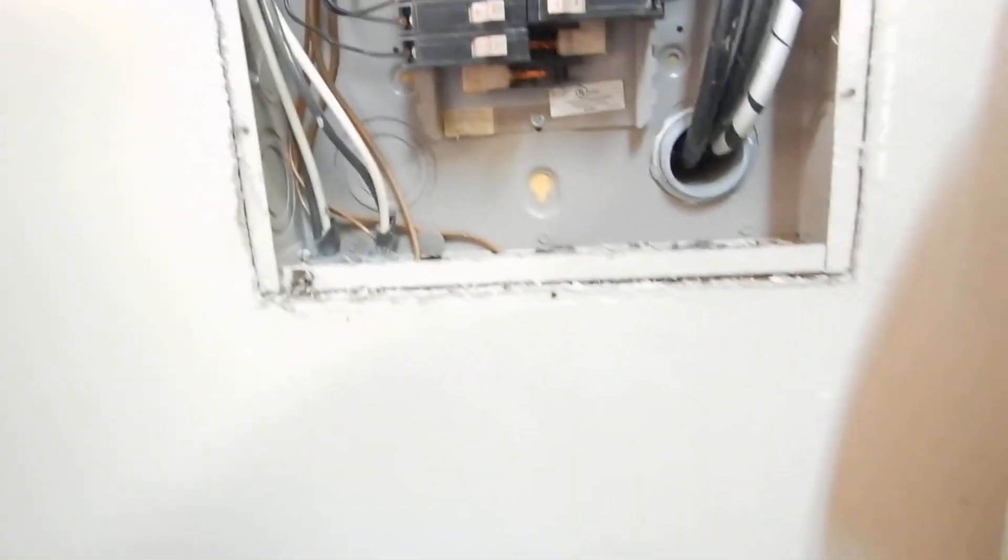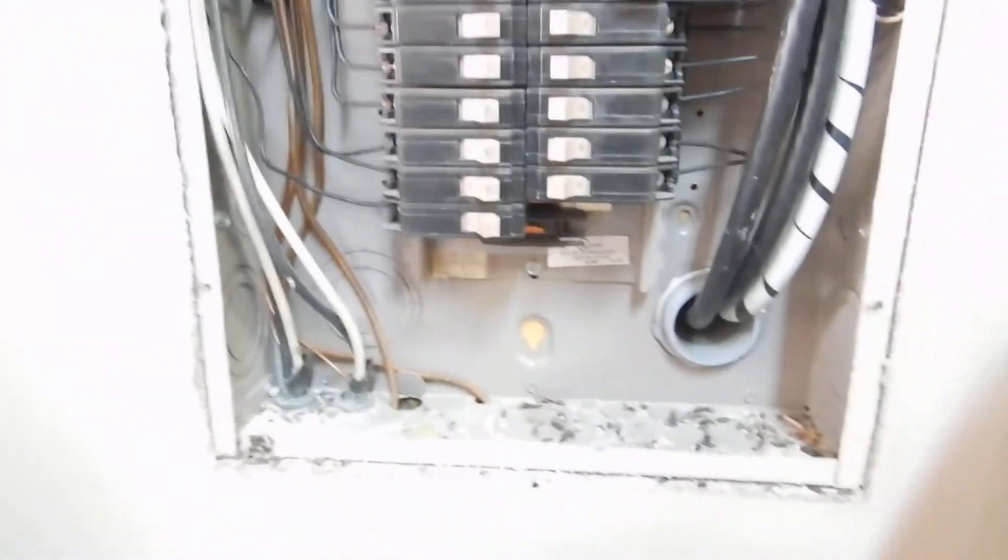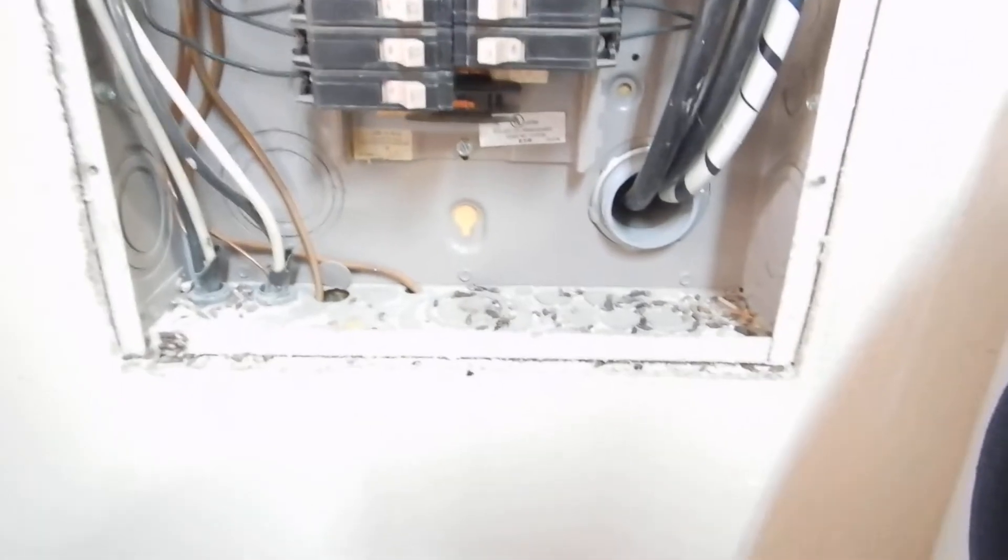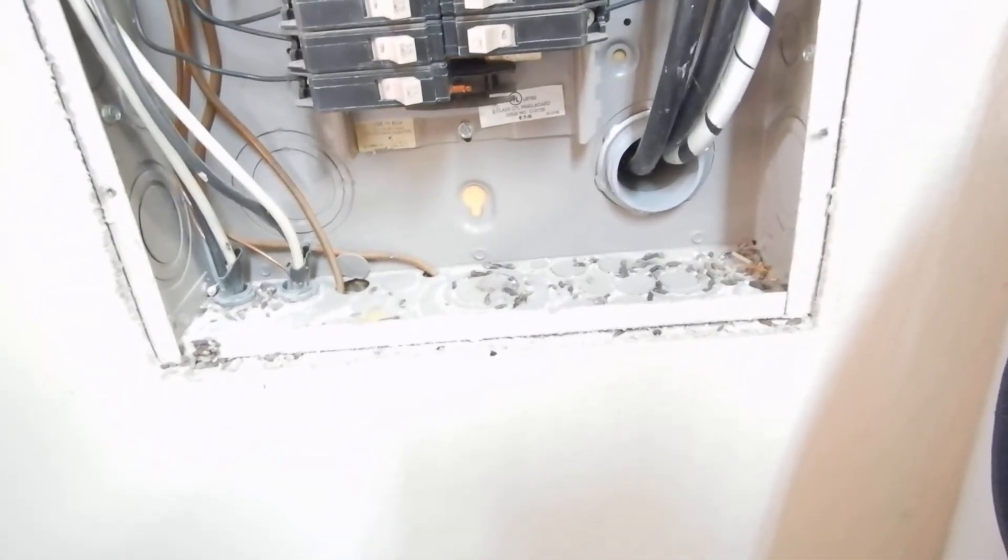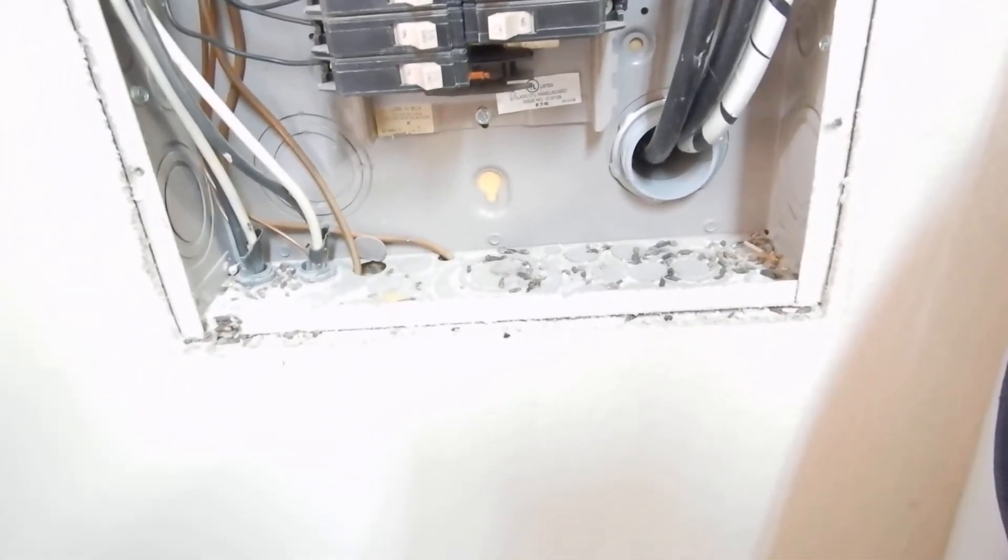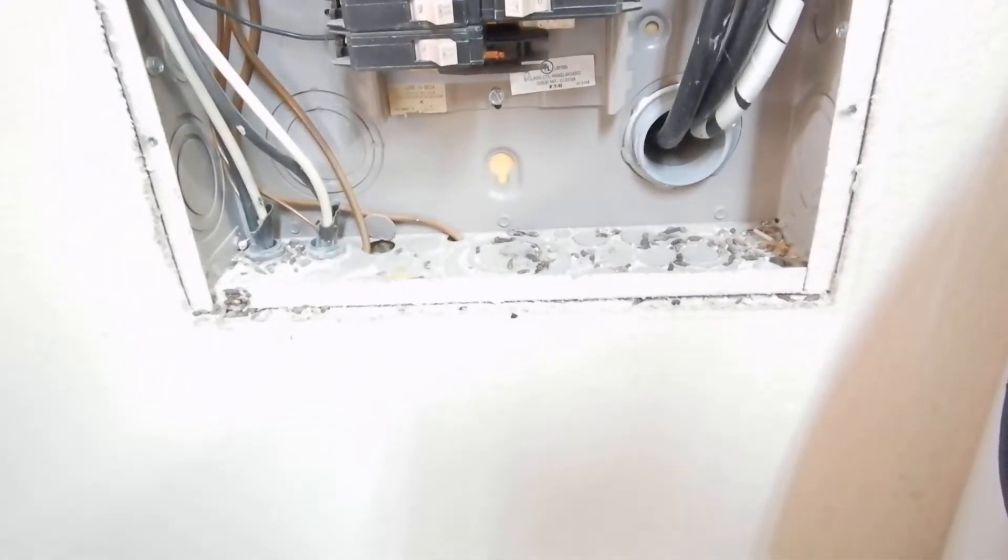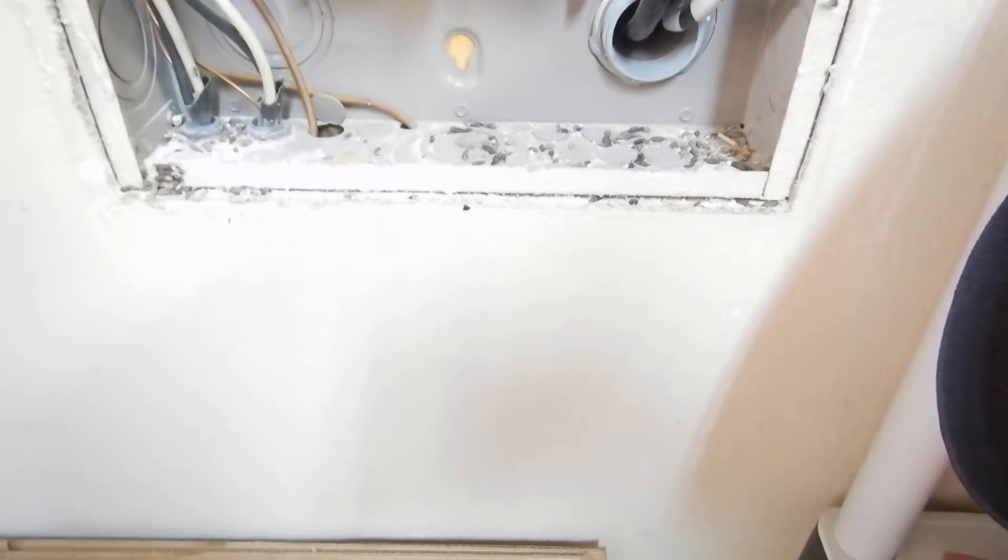What I'm not seeing here is I'm not seeing the bonding location. I usually find it at the water heater, but I've already seen the water heater. You haven't seen that video yet, but when you see it, I don't see electrical bonding for the water heater. I don't know where the electrical bonding is for this system.